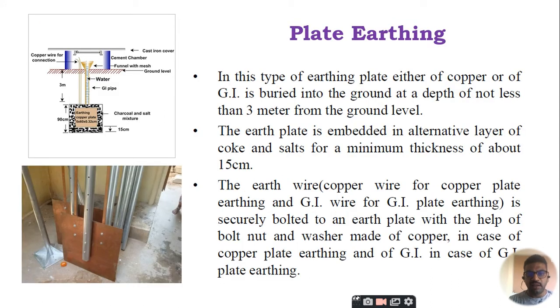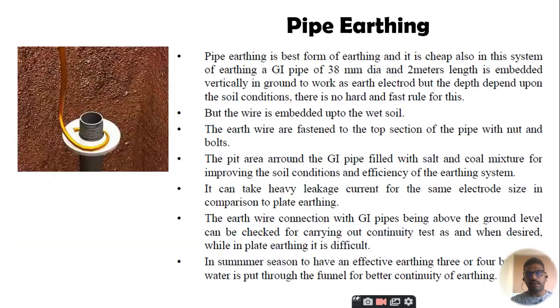The second is the plate earthing. In case of plate earthing, a galvanized iron sheet is buried at a depth of not less than 3 meters from the ground level. The earth plate is embedded in alternate layers of coke, which we call coal, and salt for a minimum thickness of about 15 centimeters. The earth wire, that is copper wire for copper plate earthing and GI wire for GI plate earthing, is securely bolted to the earth plate with the help of a bolt, nut and washer made of copper in case of copper plate earthing, and GI in case of GI plate earthing.